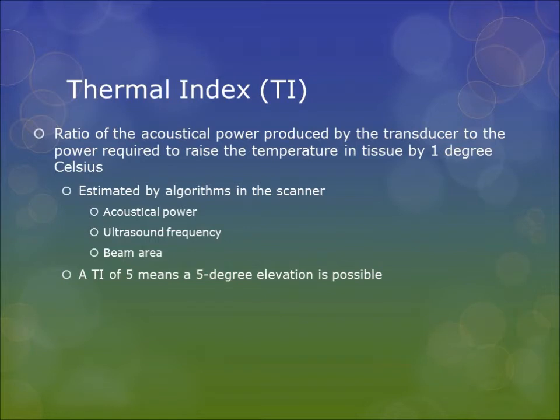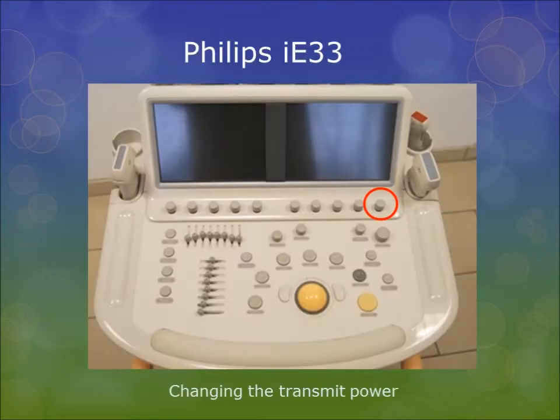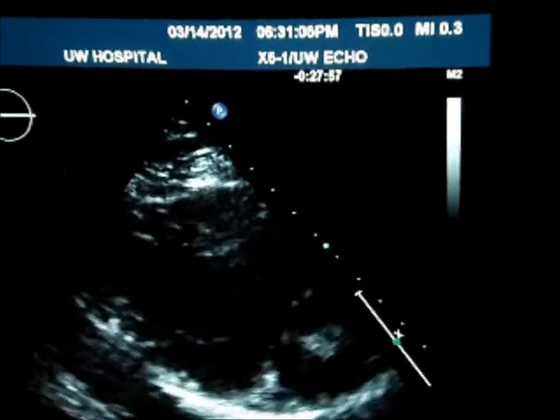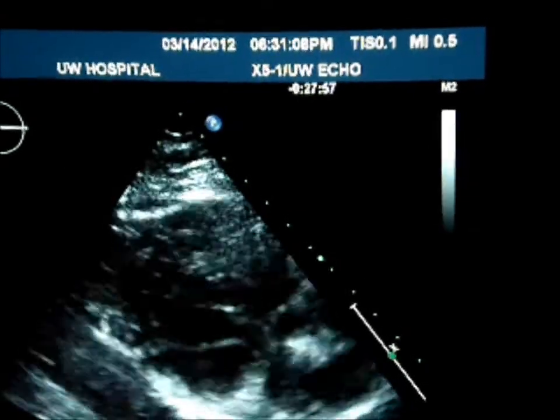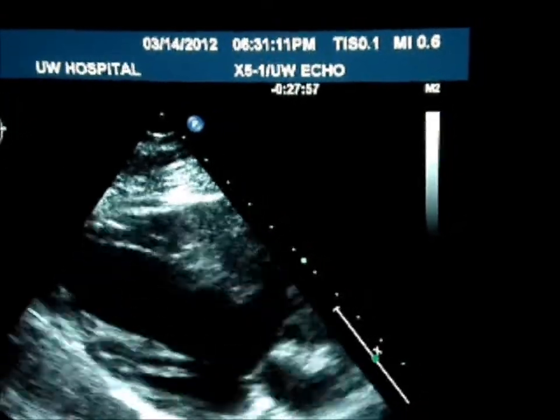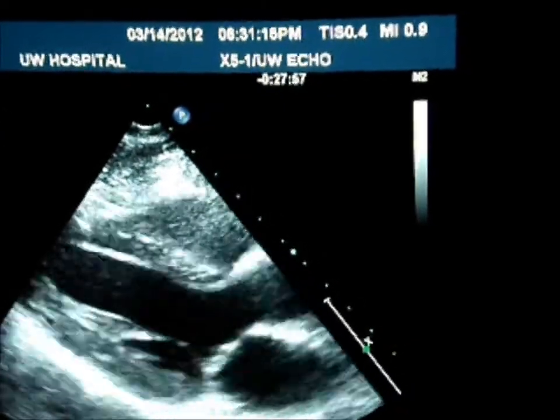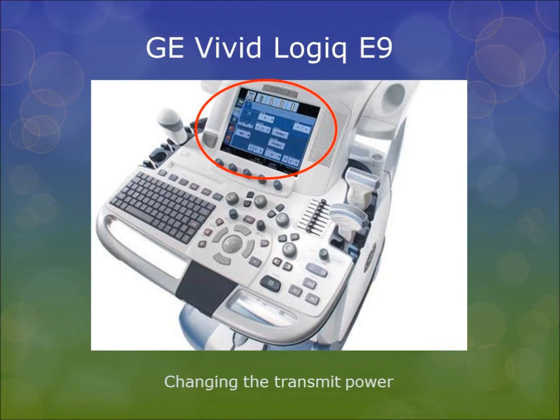Thermal index is defined as the ratio of the acoustical power produced by the transducer to the power required to raise the temperature in tissue by 1 degree Celsius. TI is estimated by algorithms in the scanner, such as acoustical power, ultrasound frequency, and beam area. A TI of 5 means a 5 degree elevation is possible. Please pay attention to the soft tissue thermal index along with the mechanical index in the upper right-hand corner. Throughout all three examples, we scanned up to 100% output. Note that the overall gain in the images either increases or decreases according to the power setting of the ultrasound machine.